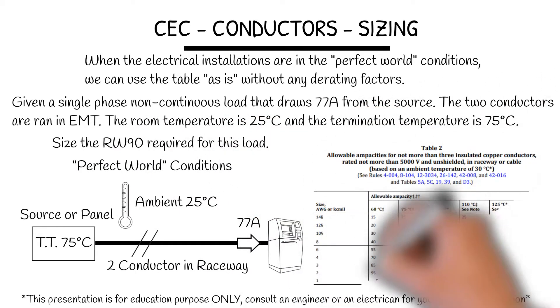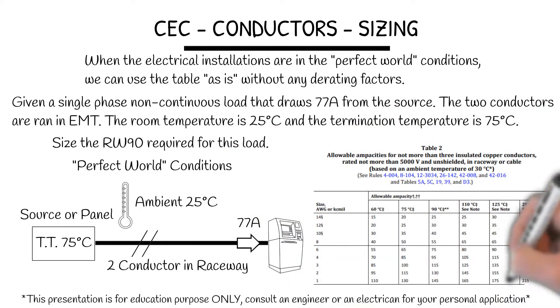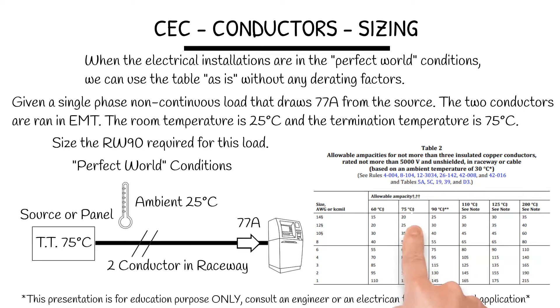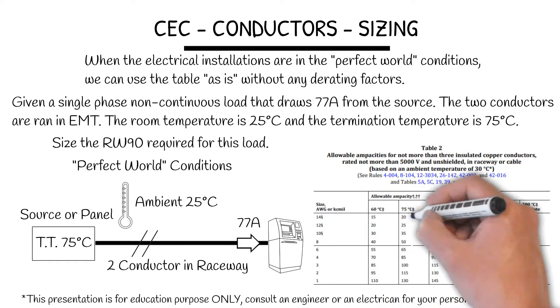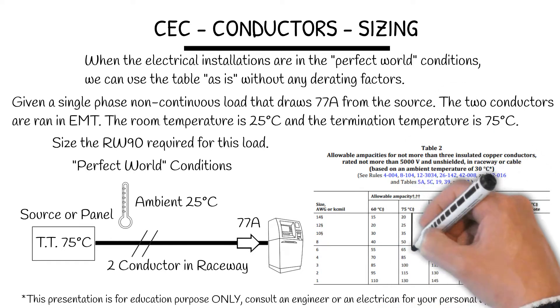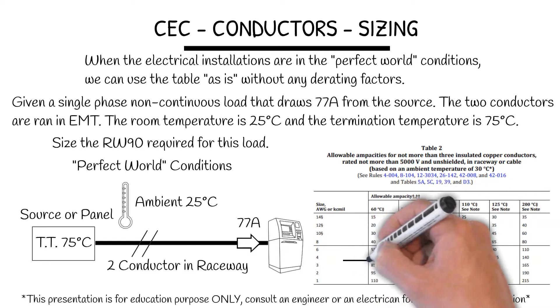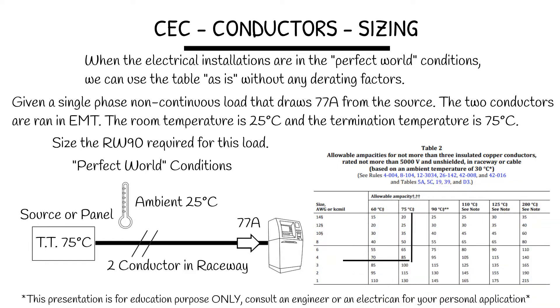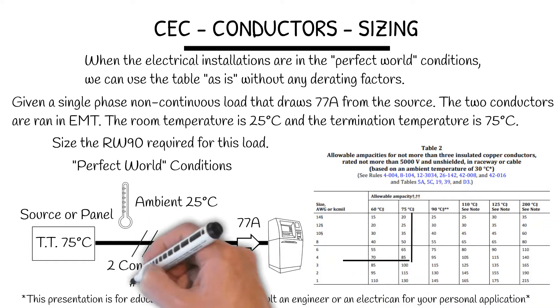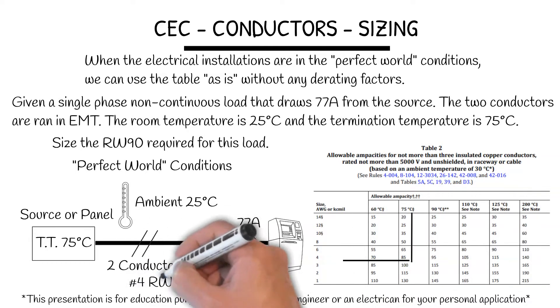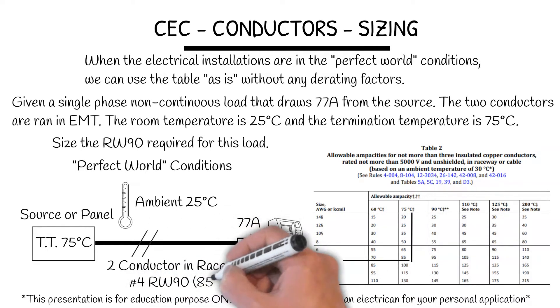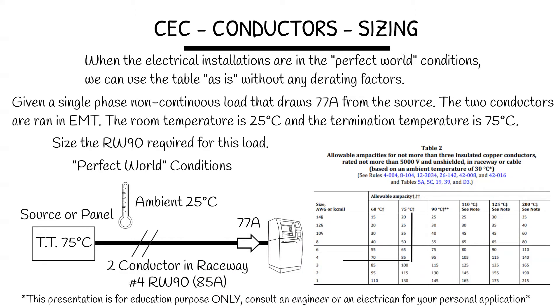Let's look at Table 2. We can go down the 75 degree column. Where does 77 amps fit? It fits on the 85 amp capacity. Therefore, we need a number 4, good for 85 amps.